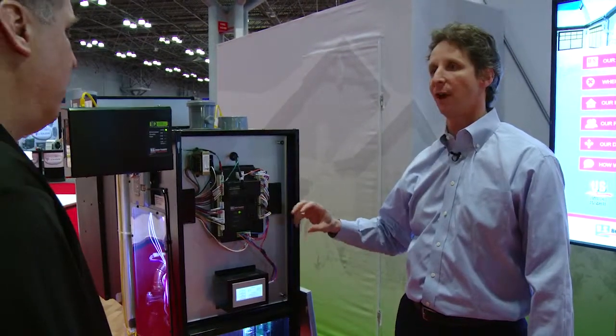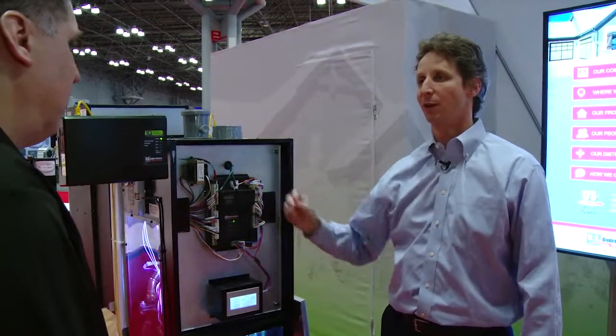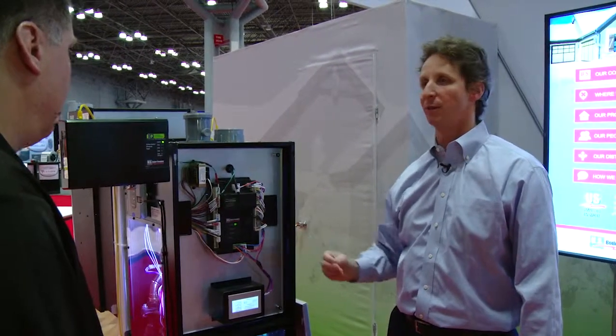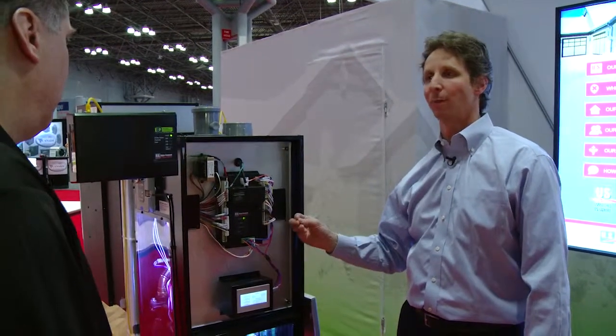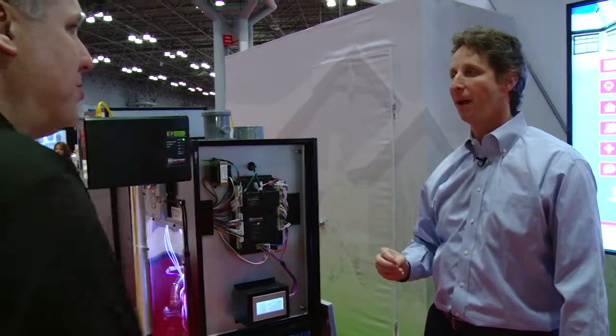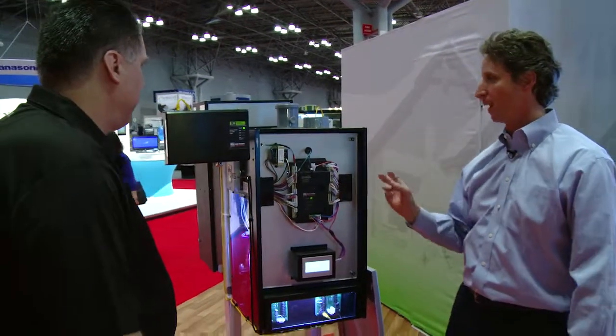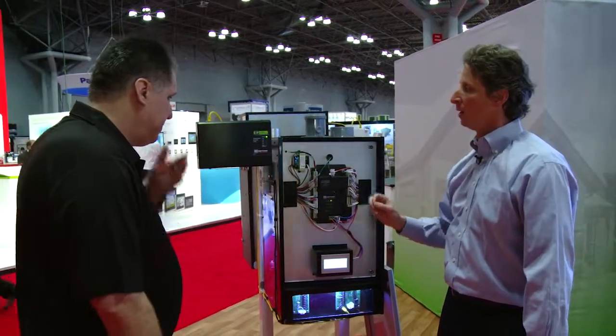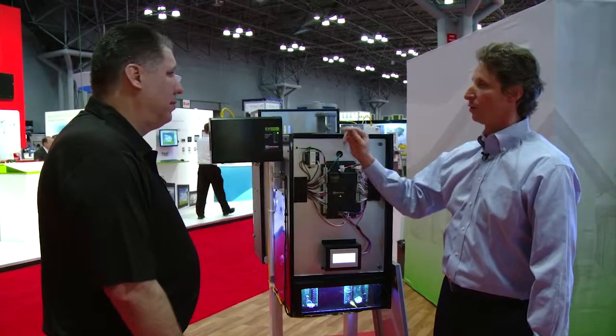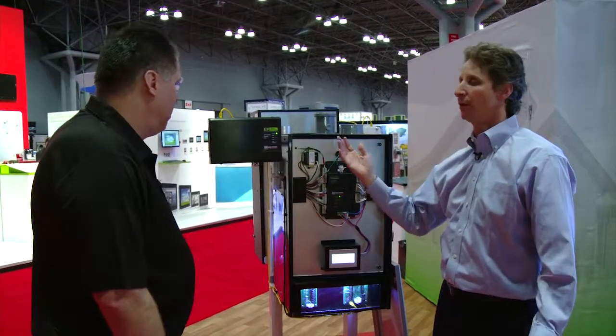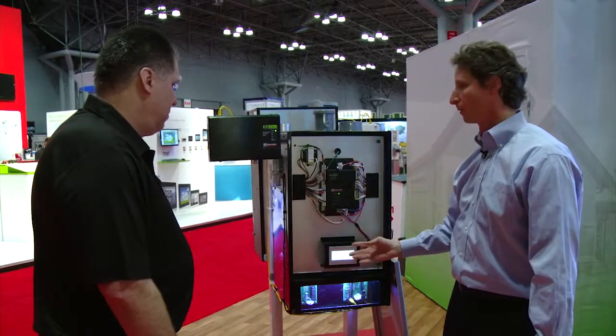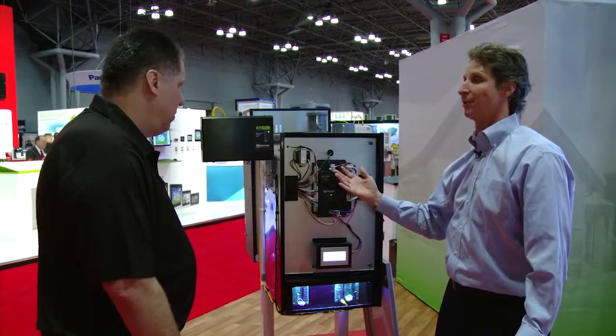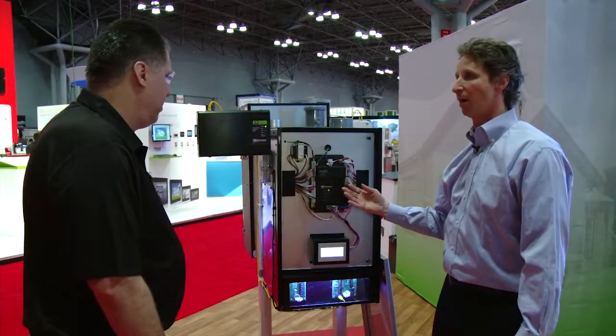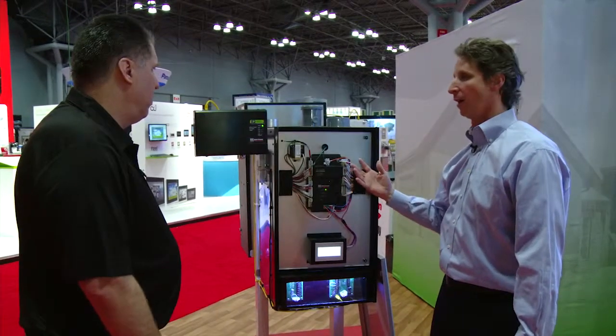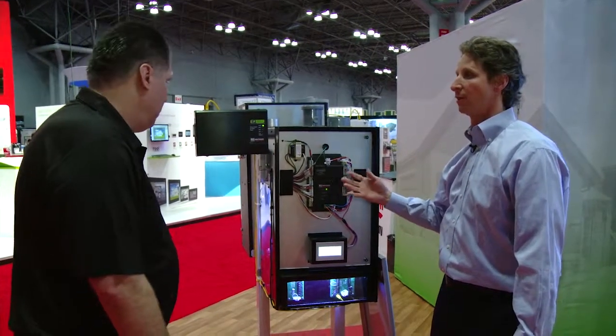It'll adjust its firing rate to only provide 20,000 BTUs of heat. It's a system efficiency thing, not a fuel combustion efficiency. So it truly is a smart control. We've got some patents pending on some of the algorithms in there. Then what it will do is, say zone 2 calls on top of it, and it's 30,000 BTUs. So now you've got 2 zones. Control says, okay, I need 50,000 BTUs of heat. I'm going to adjust my modulation rate and firing size to adjust for that.